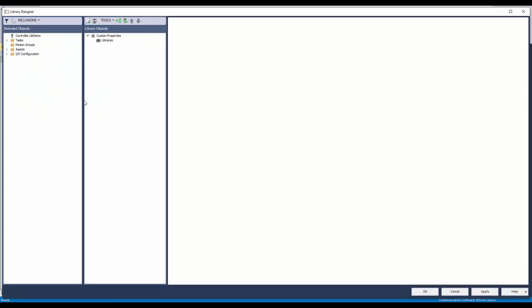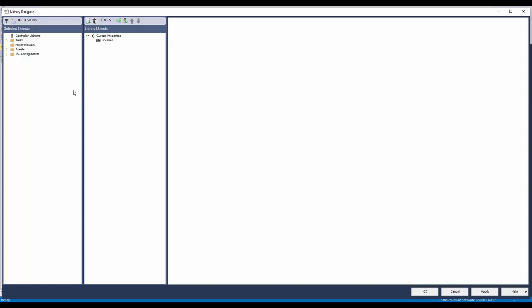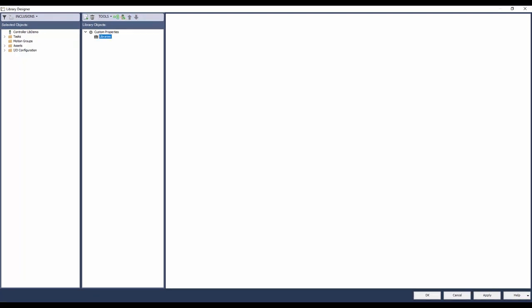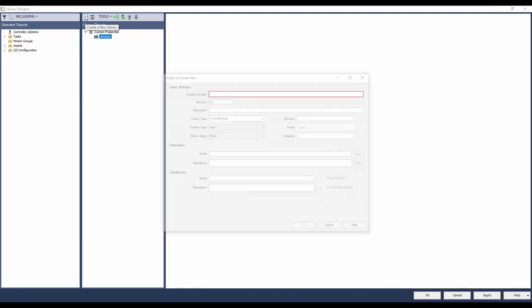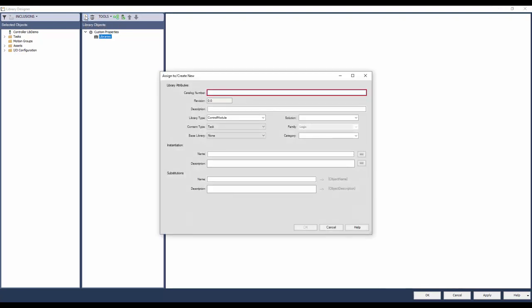Right-click on the controller and select the Library Designer application. The Library Designer is now opened. In the inclusions, uncheck the add dependency and add children options. This allows the user to manually add the dependencies that need to be part of the library. To identify the dependencies needed in the library, enable the show dependencies option. Click on the create a new library button. Enter the name of the library in the catalog number field. I will name the library as RAM Device Valve.